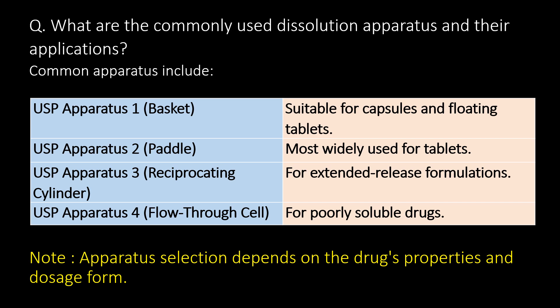What are the commonly used dissolution apparatus and their applications? USP apparatus 1, basket type, is suitable for capsules and floating tablets. USP apparatus 2, paddle type, is the most widely used for tablets. USP apparatus 3, reciprocating cylinder, is used for extended release formulations. USP apparatus 4, flow-through cell, is used for poorly soluble drugs. Apparatus selection depends on the drug's properties and dosage form.